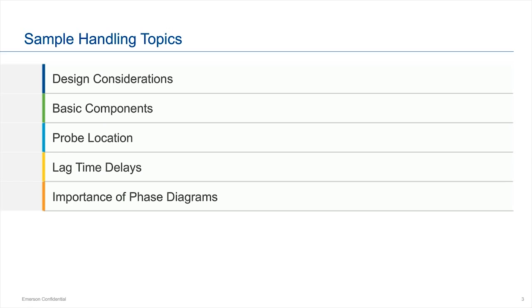We're going to do a quick review of design considerations, then go into the basic components. We'll spend a little time on probe location — that's critical because the GC works like garbage in, garbage out. The probe is your first part of the sample handling system; if you get it wrong there, it won't be made up for later. We'll also cover lag time delays and the importance of phase diagrams.